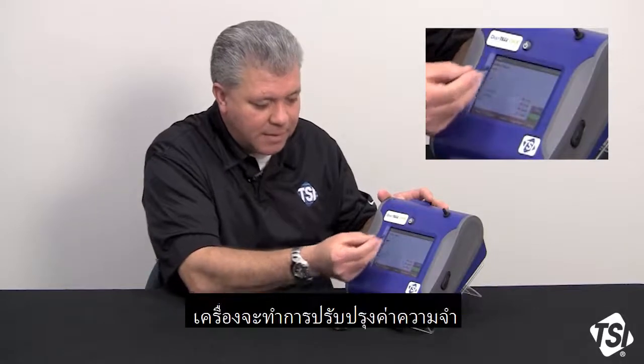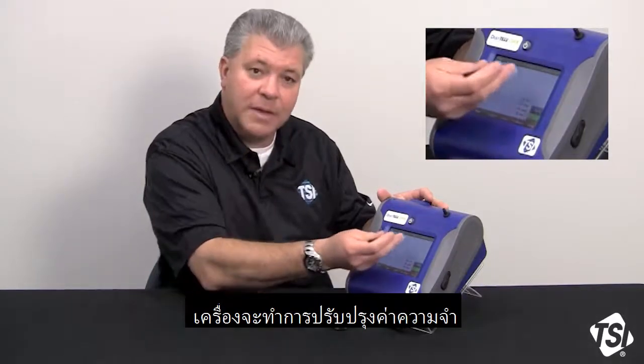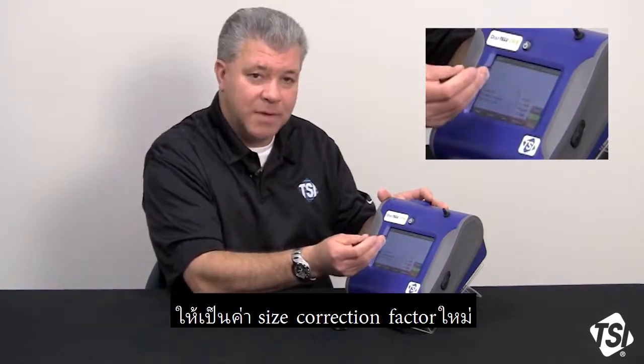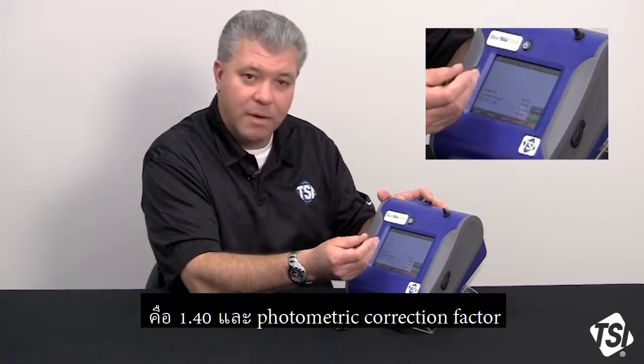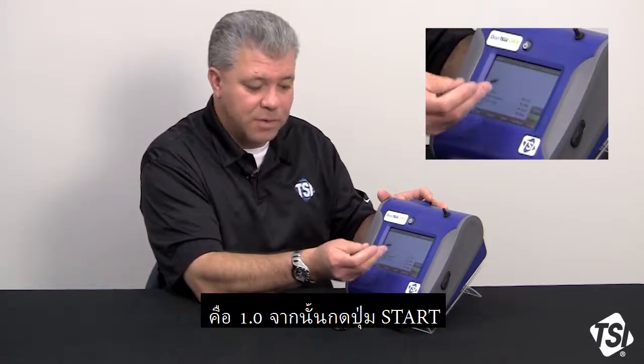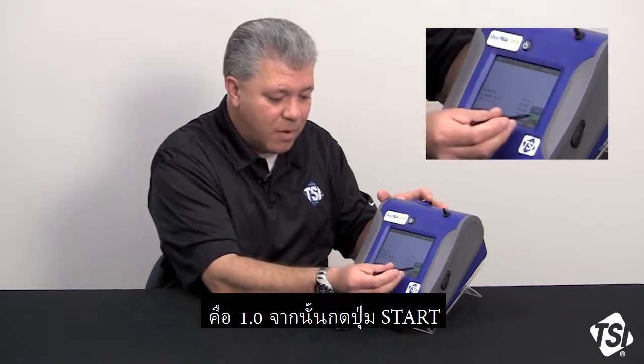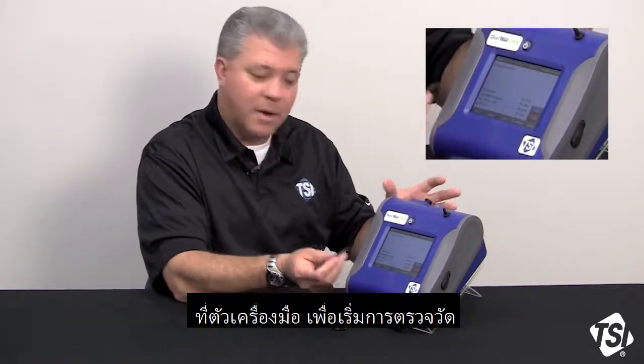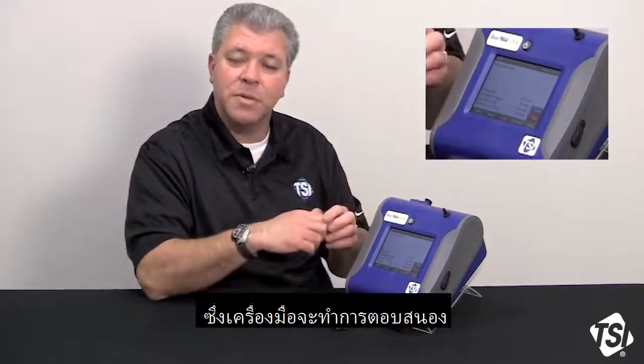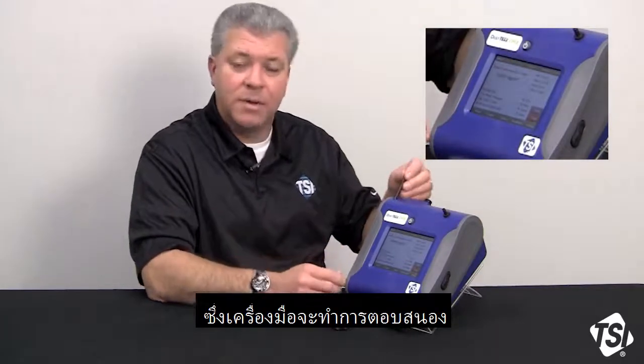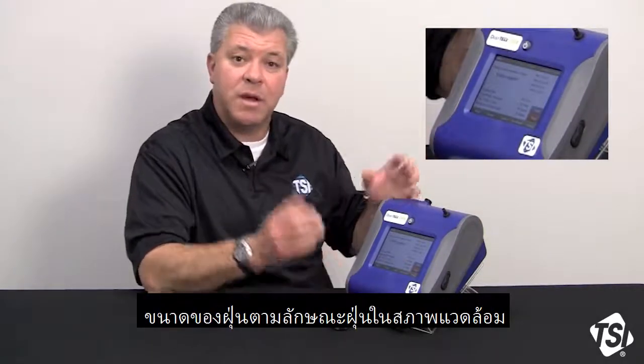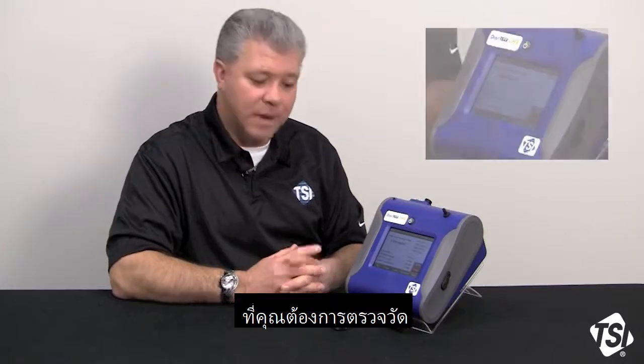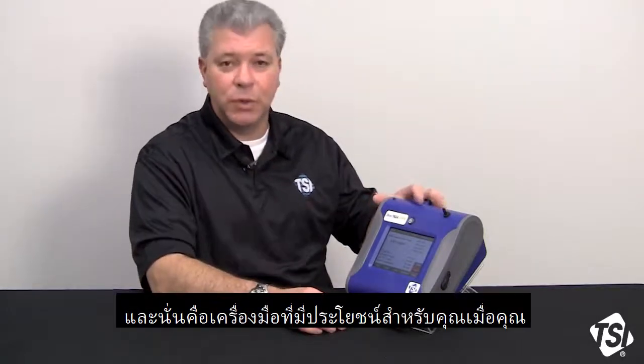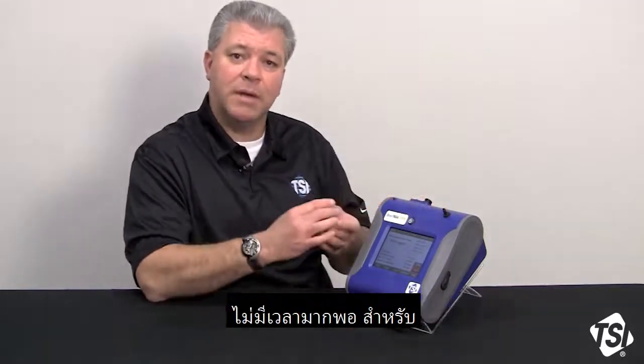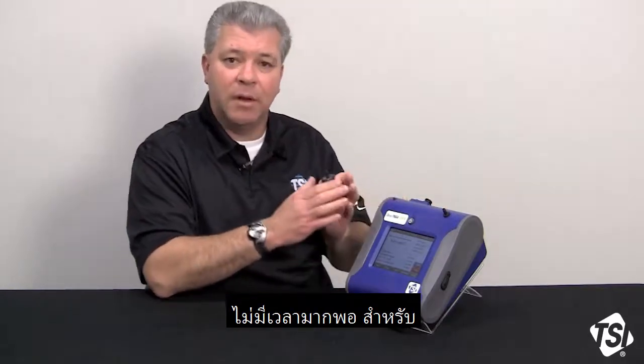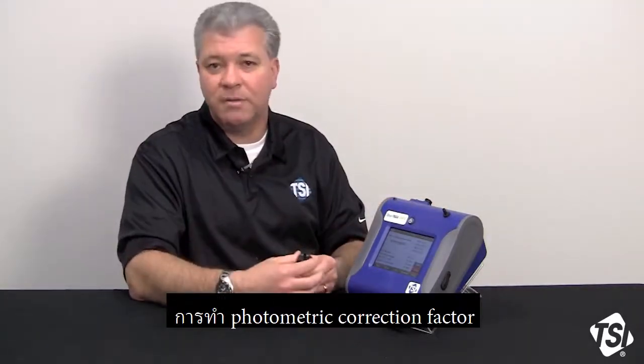It's going to update the memory, so now it's inputting in that the size correction factor is 1.4, the photometric correction factor is still 1.0, and now when you press the start button, the instrument turns on, the instrument's response has changed to the size distribution of the aerosol in the environment that you're monitoring. So a really useful tool when you don't necessarily have the time to do a long drawn-out photometric correction factor.